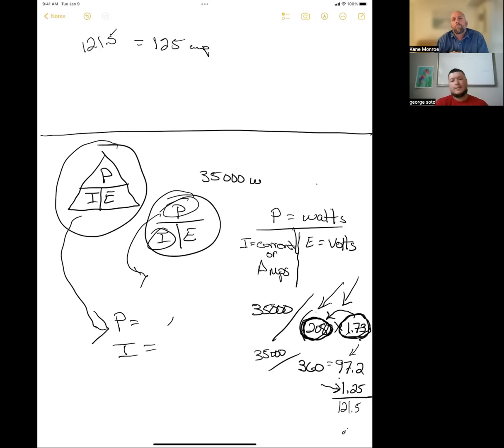So if it's a general purpose transformer, it's just being fed backwards. Yes sir, and I think it's feeding a 100 amp motor load, 100 amp on the 480 volt side. Woo, what's he bringing in on the low side, on the 240 or whatever? What do you mean bringing in, like overcurrent protection, those conductors have got to be huge. 400 amps? 400 amps. You're breaking up. Yeah, 400 amps. Yeah, that makes perfect sense.